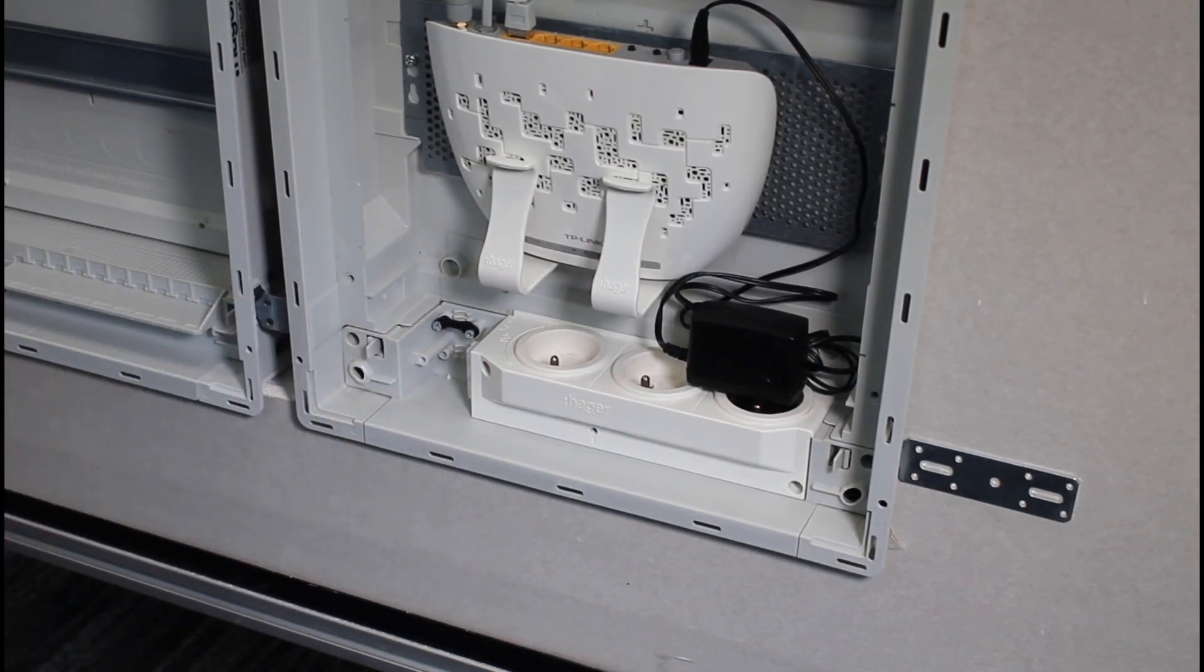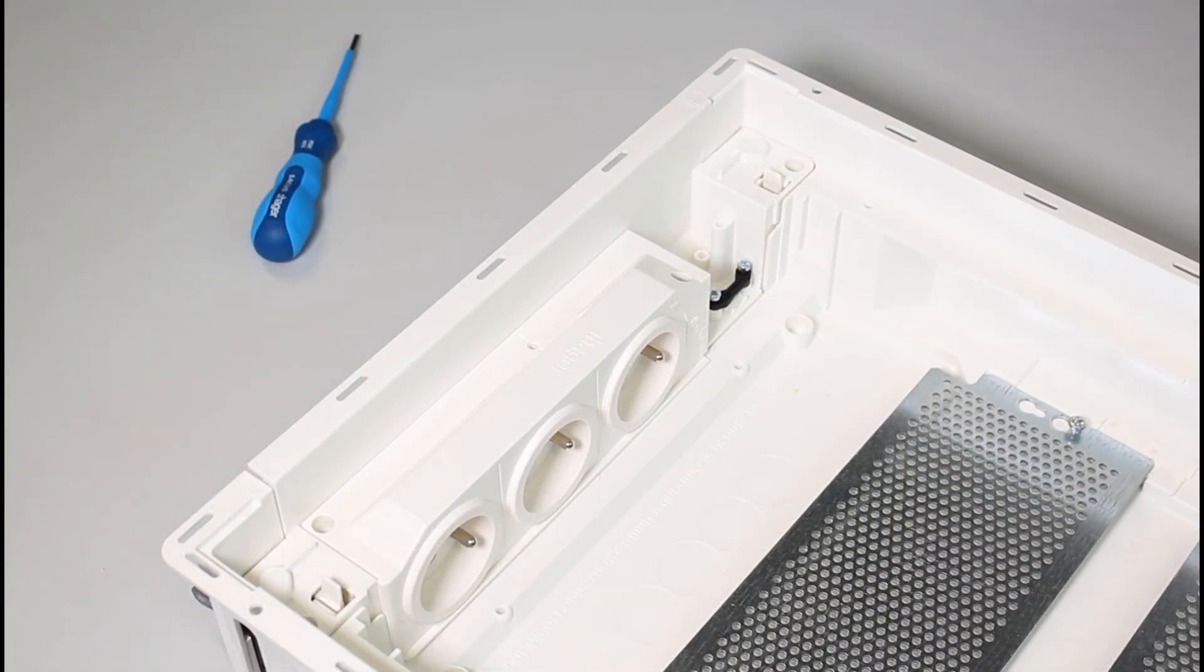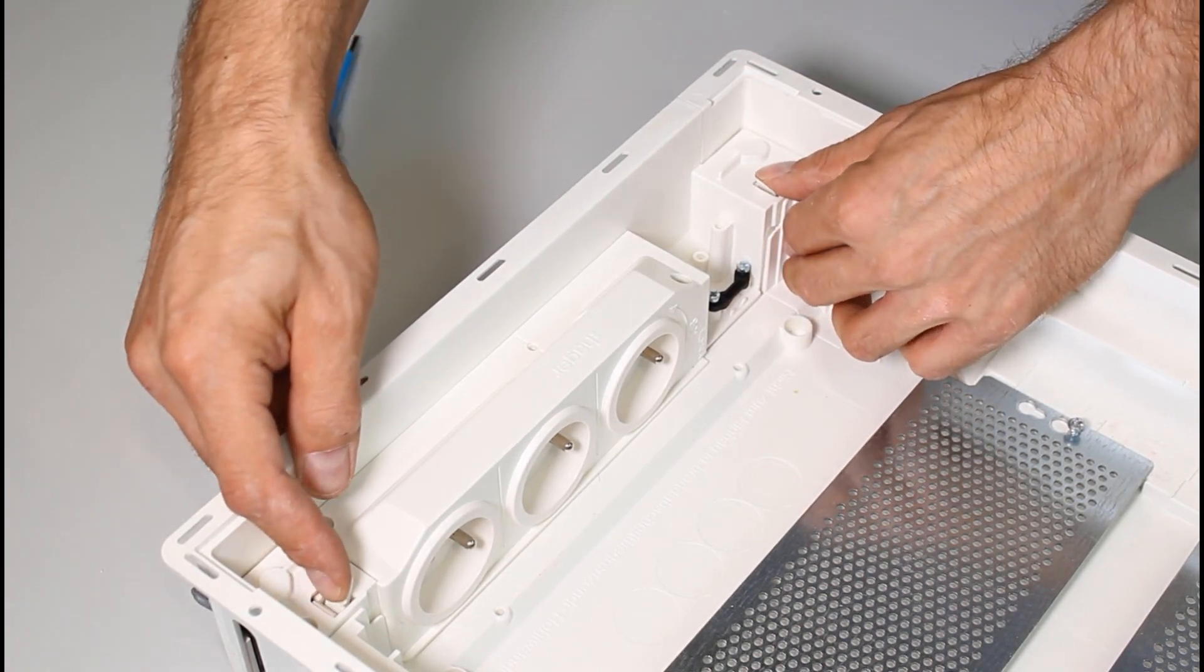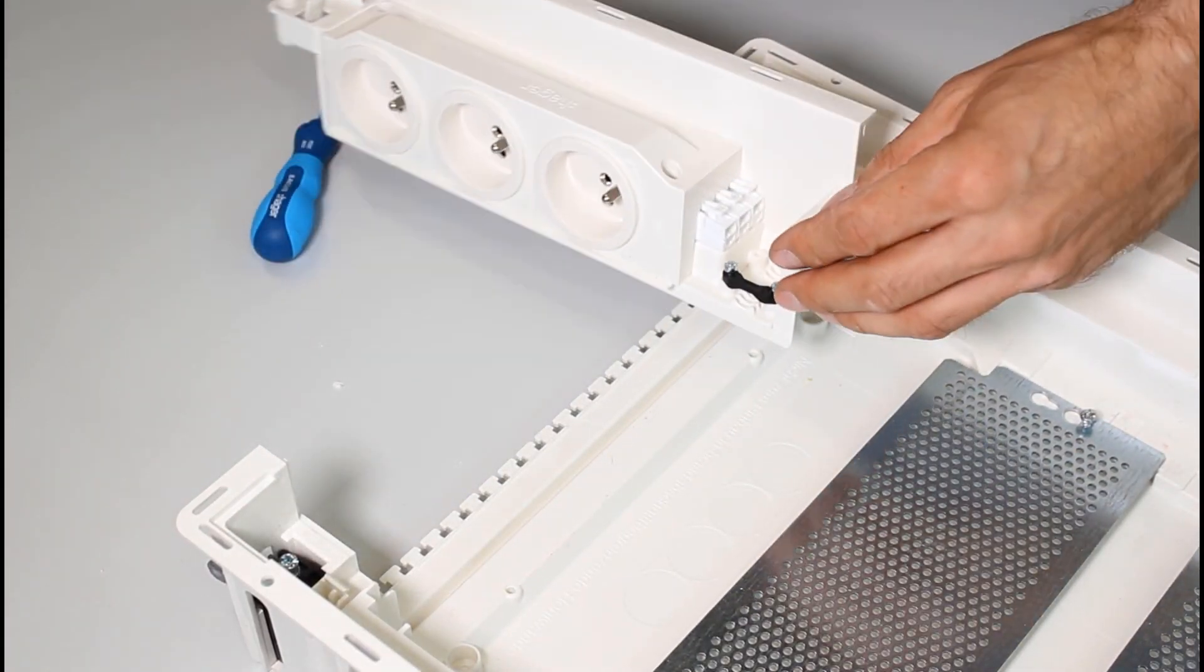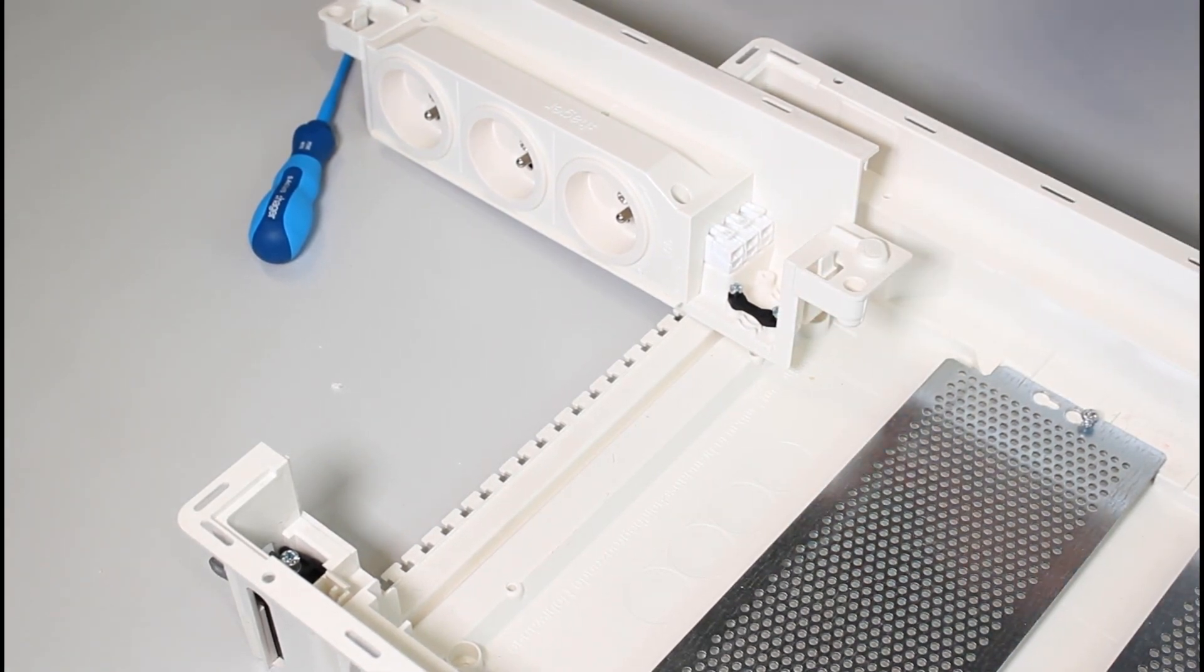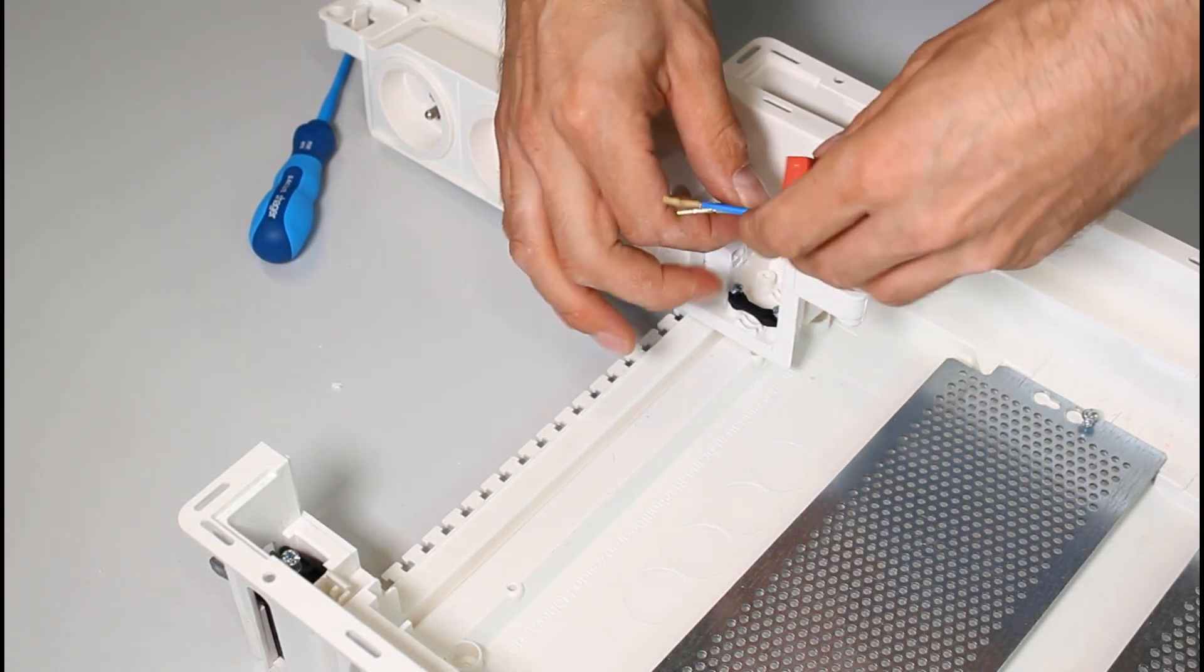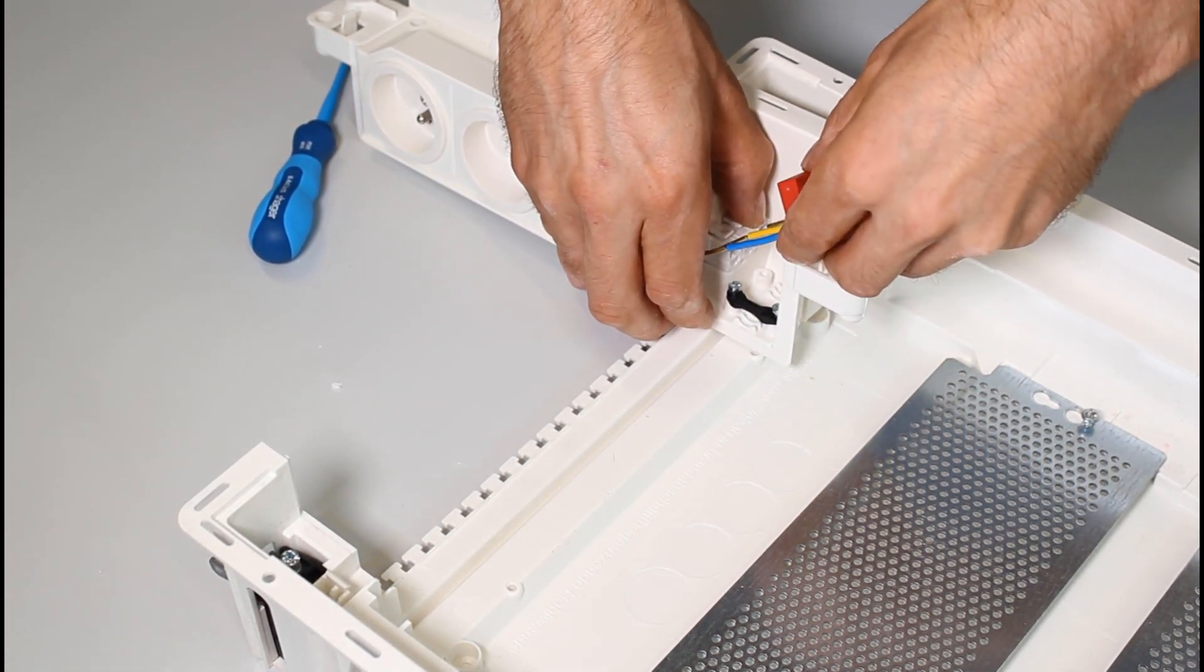A special space is provided with connection accessories. To increase the reliability of the power supply and overall functioning, an additional surge protector can be used that reduces the surge voltage to 1.5 kV. The original type 3 protector is designed to be installed without the use of additional tools.